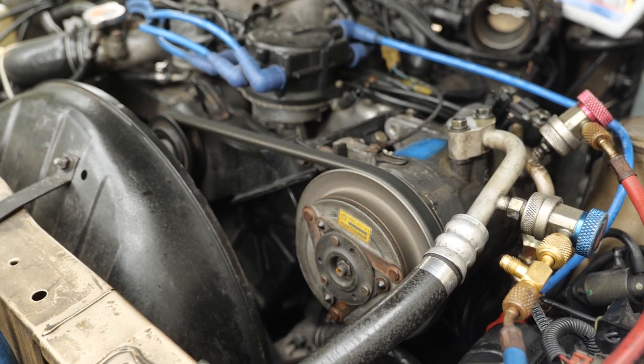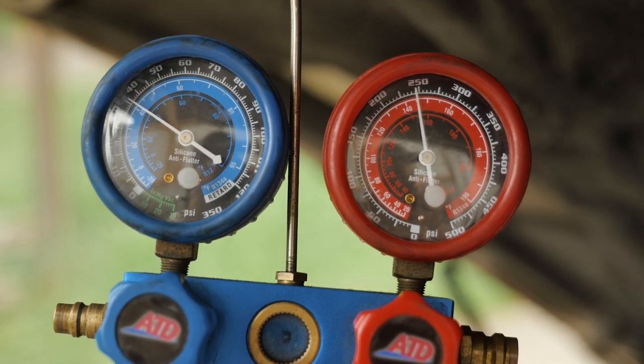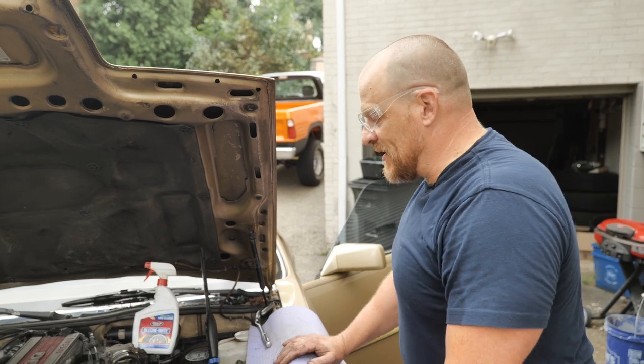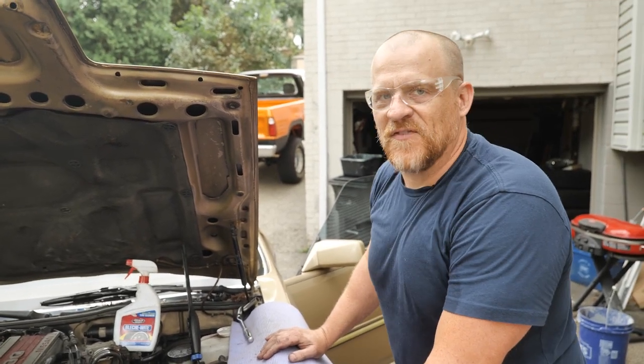You ready? Okay, you went to 250 and then like 35. Hell yeah. To get 250 on the high and 35 on the low, you know, that compressor is great. That makes me feel wonderful, all warm and fuzzy inside.